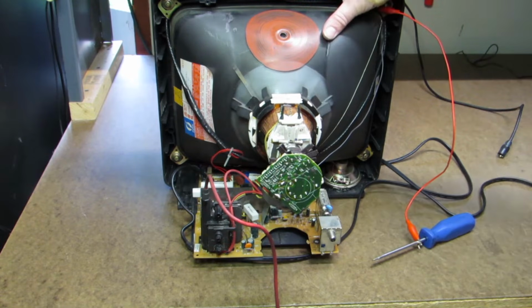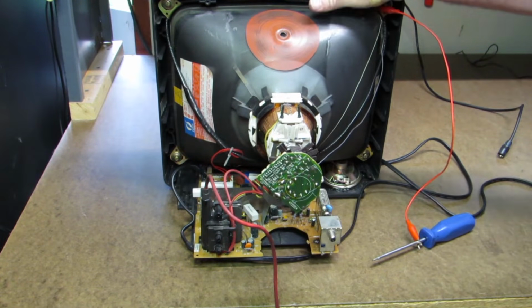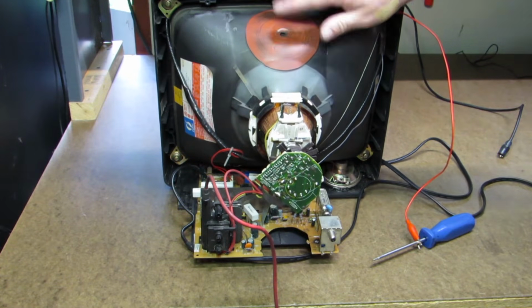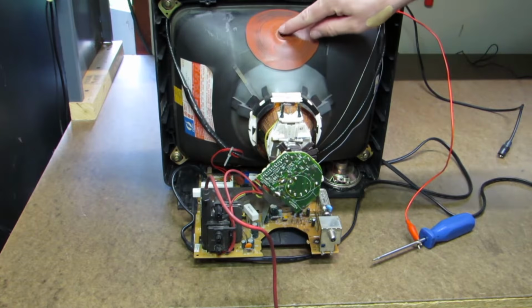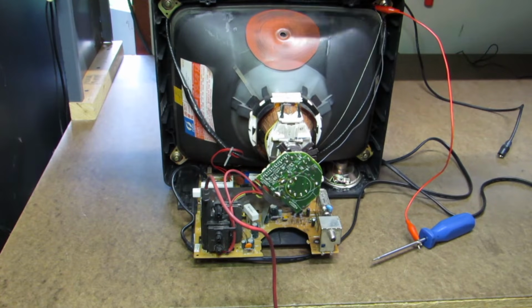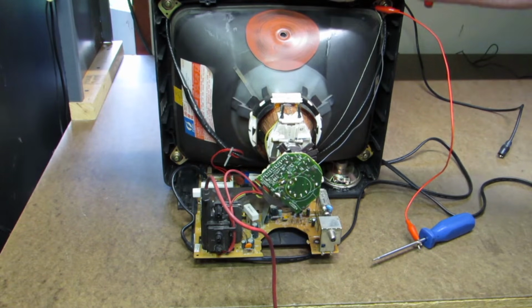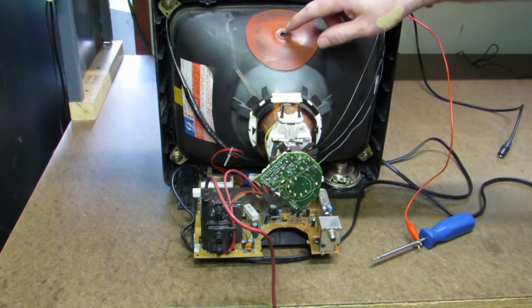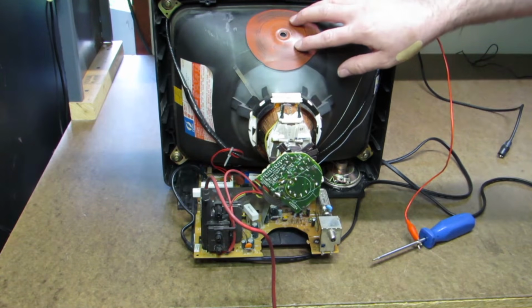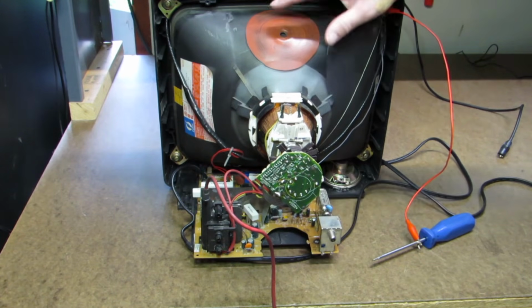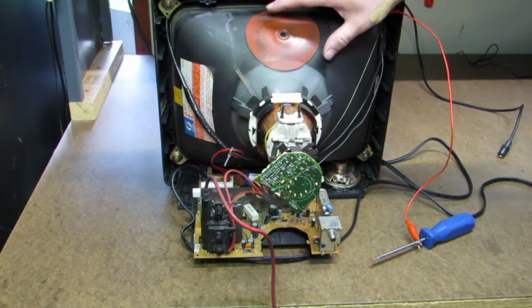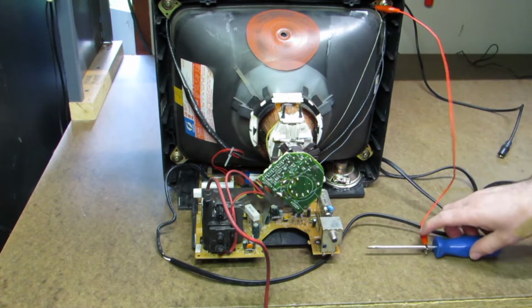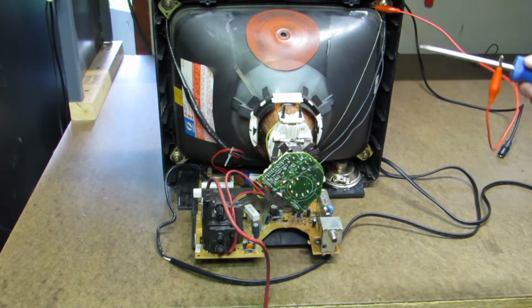One thing to be mindful of is that some larger tubes, like 25-inch, 27-inch, and other big stuff, and even small tubes to some degree, this can sort of start to recharge in the same way that certain large capacitors do. It's not a big deal. It's not going to hurt you. Just be mindful that there might be a charge that comes back to this after it's been sitting unhooked for a while, but it'll be minimal. It'll be like getting zapped by a doorknob or something. Now that that's disconnected, this is safe to work on.